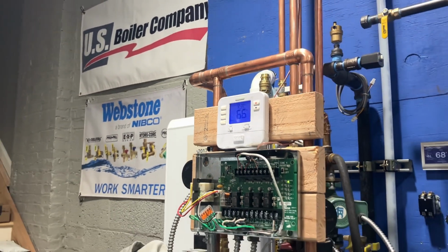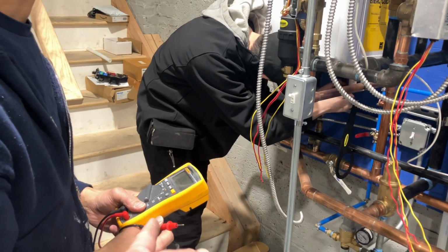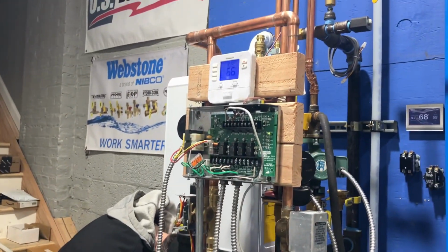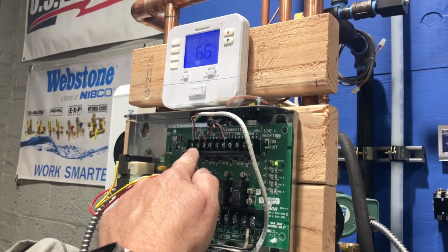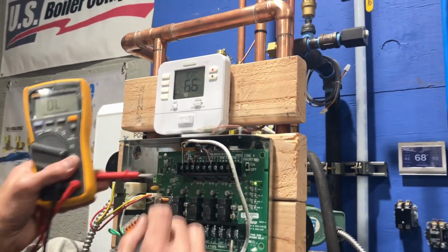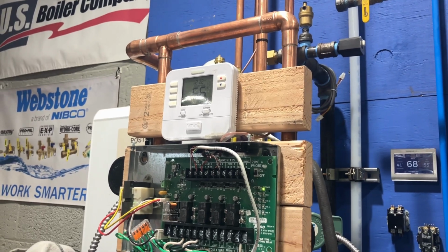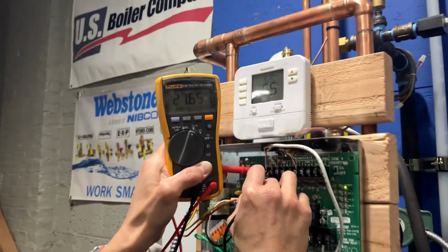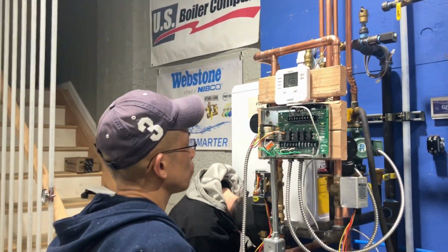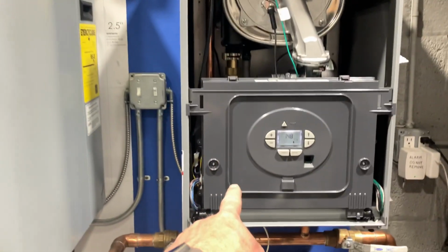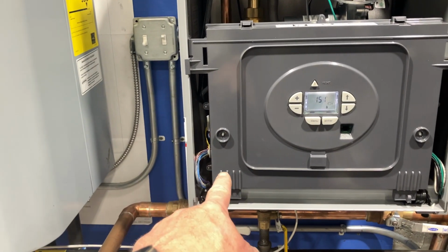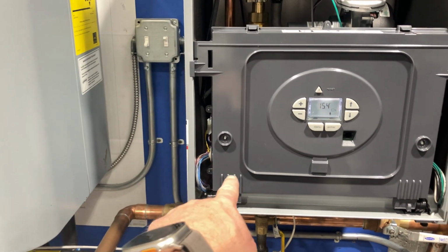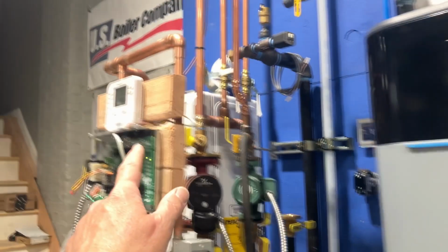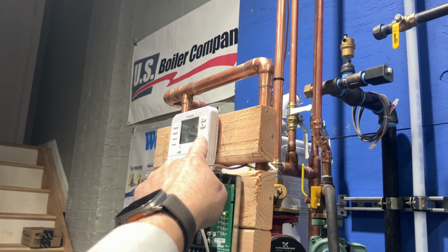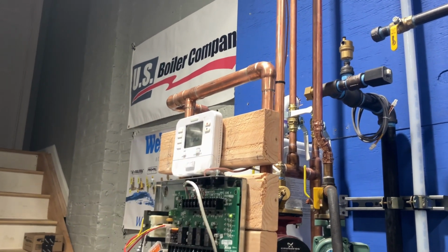No longer continuity. No. We heard the ticking of the multimeter because it's connected to something on the boiler. It's connected to 24 volts. Measure here, voltage. We have voltage there. Why do we have voltage there? We have voltage there because we're connected to R and W, or TT, on our boiler. There's power there. And that's another reason why you have a jumper between RH and RC on thermostats.